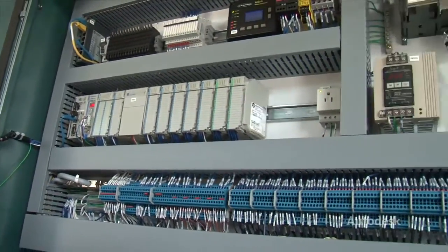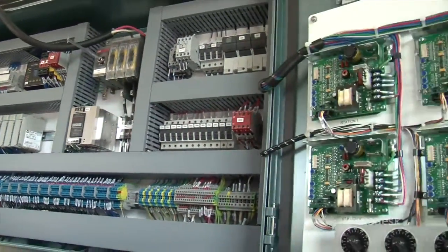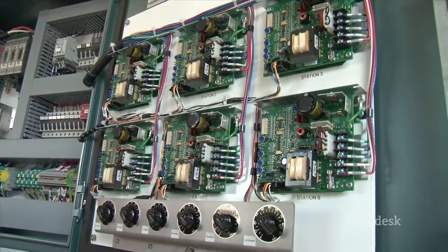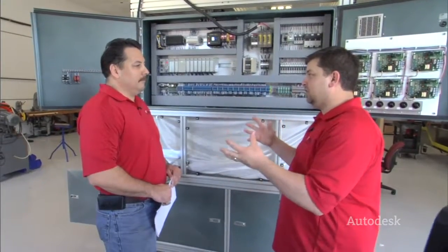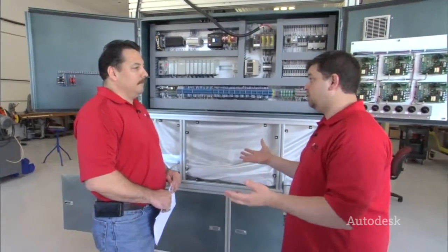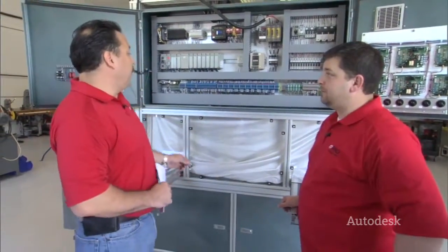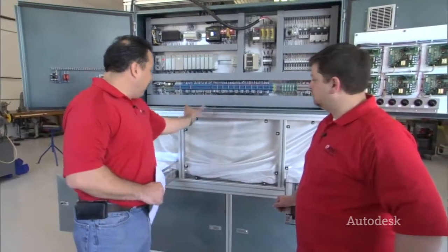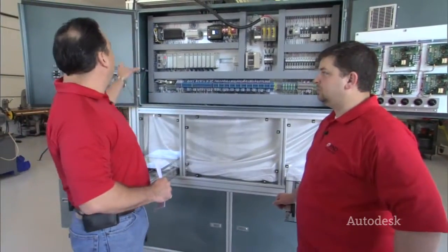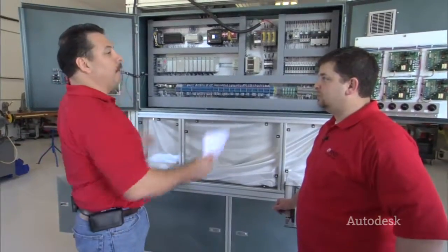So how do you take the ins and outs and the lead-ins and the lead-outs and your home run wires and document those? I'm assuming you're using some form of AutoCAD to be able to do that? Correct. Well, there's two parts to that. For the Inventor side, we actually have wireway on the machine, and the machine enclosure is actually part of the machine frame. So the guys will model that in their drawings and come up with the main wireway drops. At that point, it's custom design. We'll find the best routing for all the cables for the field devices.